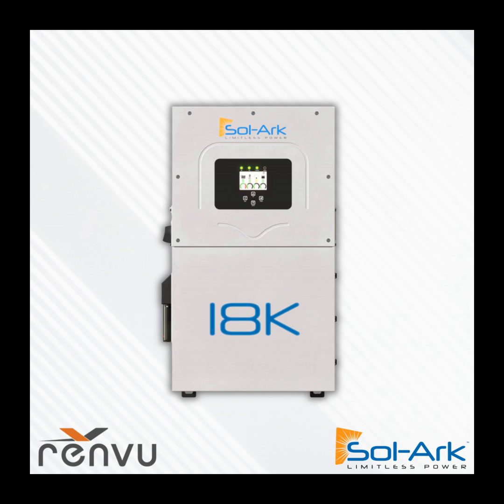When installing mechanical bypass, the Sol-Ark recommends switching the neutral as well as the line voltage in a 240 volt split phase system. I would only switch the power conductors and I would keep the neutral connection from the utility transformer passing through to the main service panel. So you're really not switching in a bypass scenario from the grid to a generator. If you want to do that, you can use the gen port. If the grid relay fails and you want to add additional redundancy, having a generator there is another way to risk mitigate.